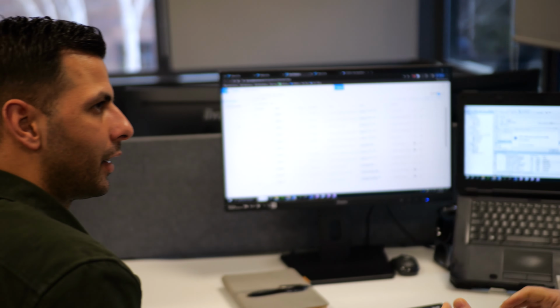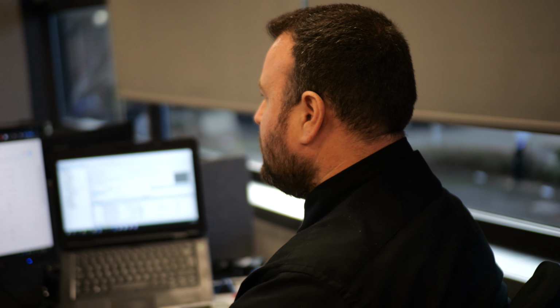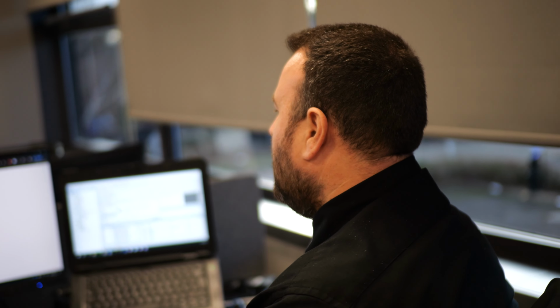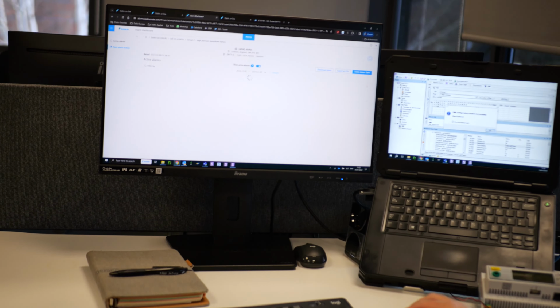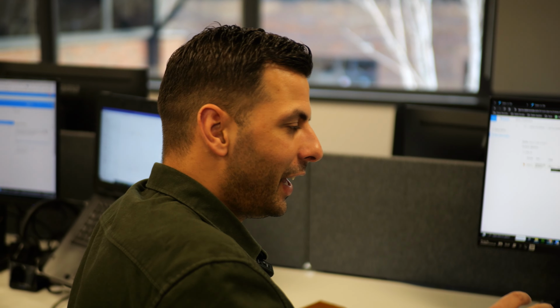That's right. So there's also the alarm ticketing system that is automatically generated, so you can choose an alarm that was generated. Not all the alarms have a description yet, but you can see. So I'm looking at this, and when we use the word AI, or even going back to the Airnet with a logic module, if you've put into the logic module what parameters or limits need to be in place for it to be a low refrigerant alarm, as in it's got low refrigerant. Yes. It would. But then saying that, you're going to get the fault code on this anyway, aren't you?